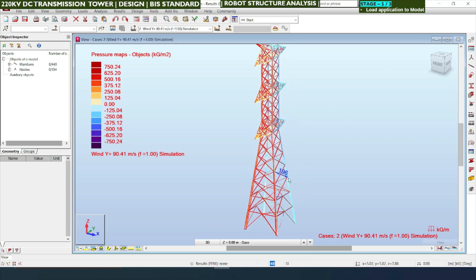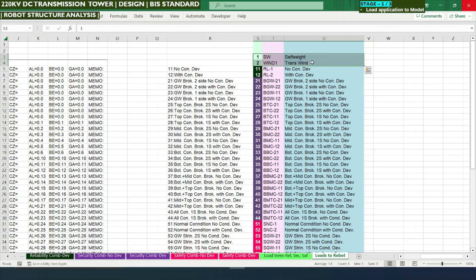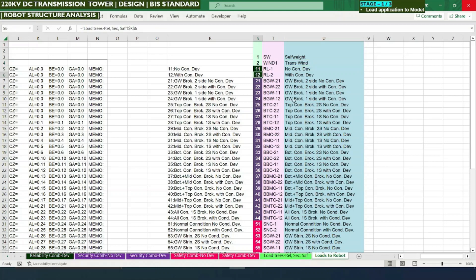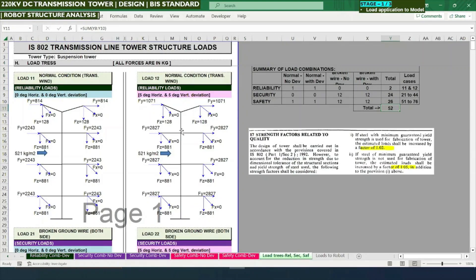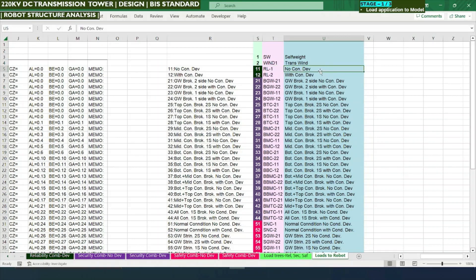Now we apply loads on the conductor and earth wire. For the conductor loads we need the Excel load tree. Load cases 1 and 2 are self-weight and transverse wind of the tower. Load cases 11 and 12 are reliability level cases. The green color cells represent reliability load cases — RL1 is the symbol for reliability load with no conductor deviation, and RL2 is with conductor deviation.